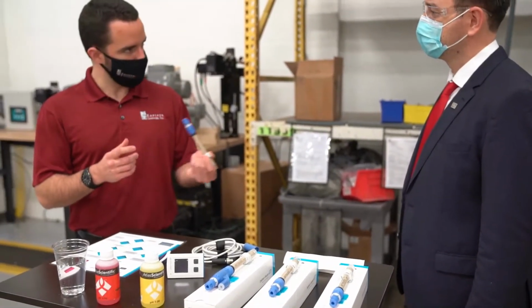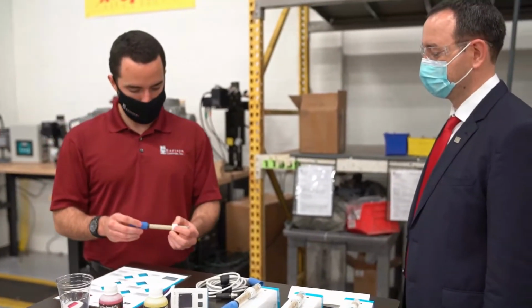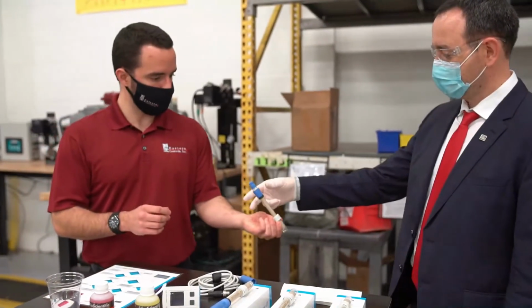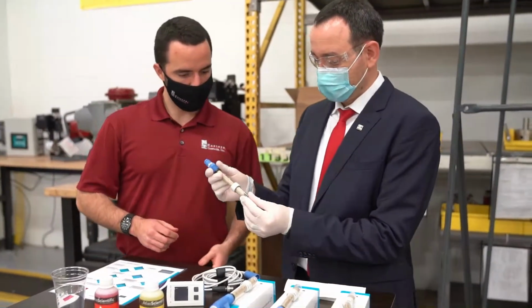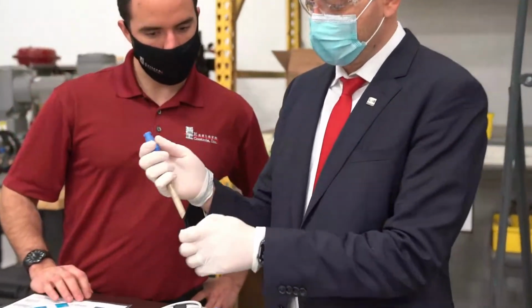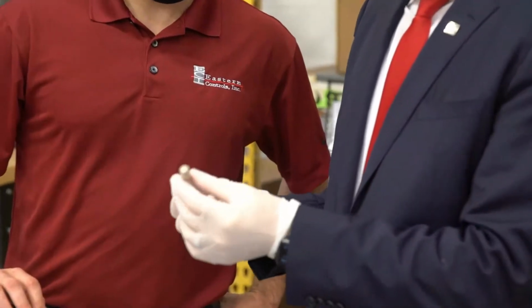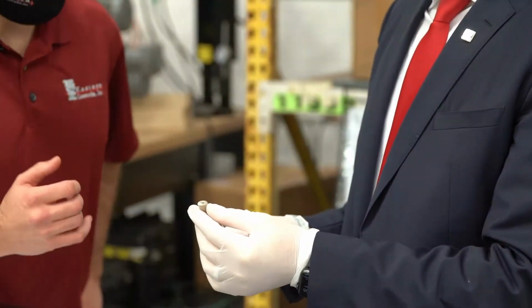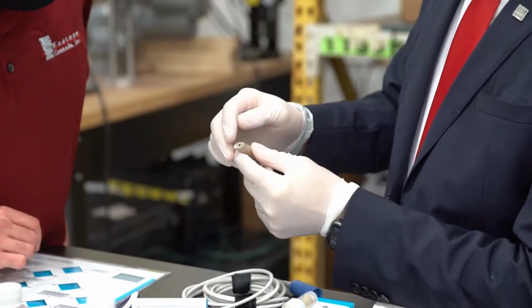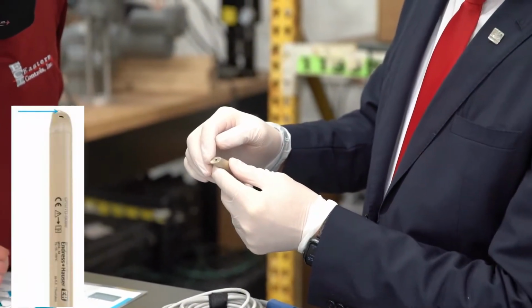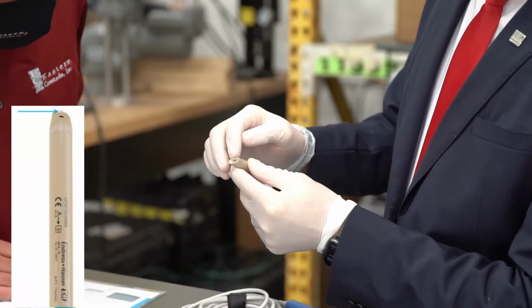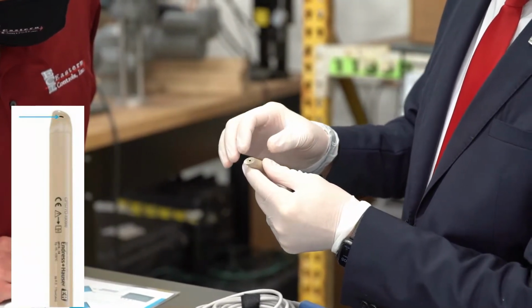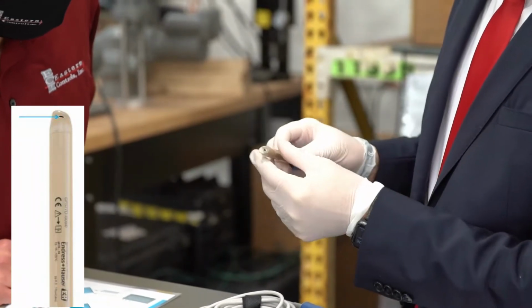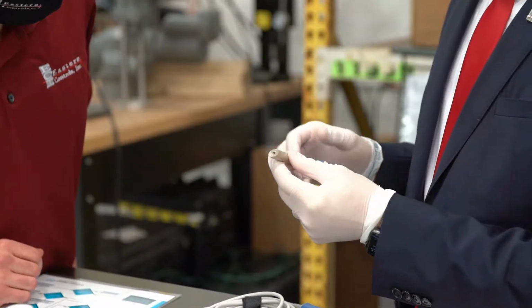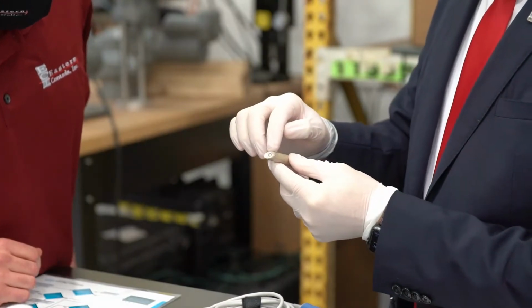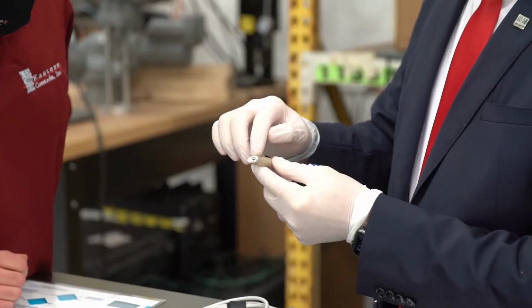So Agent 77, here's our bad probe. Needs cleaned and calibrated. Do you mind showing us? Sure. So first we take it out from the protection cap and we visually check if it is clean or not. We check the reference junction. And then we check the measuring point, basically the tip of the probe where the measurement happens. This is valid for glass probes as well. This is a non-glass, but we need to maintain the tip of the probe completely clean.